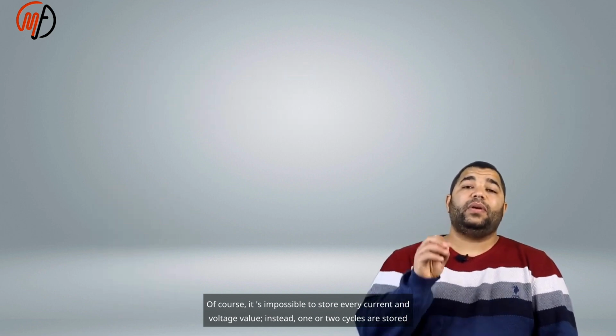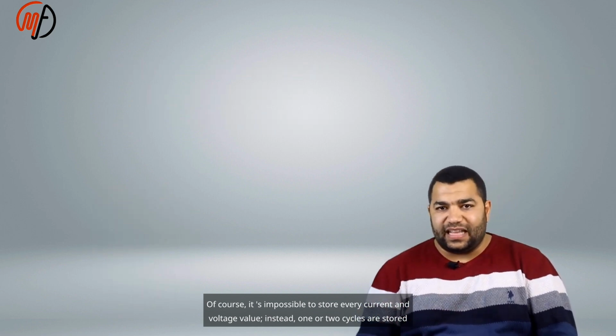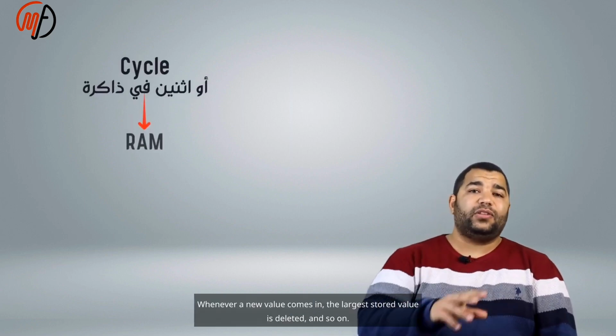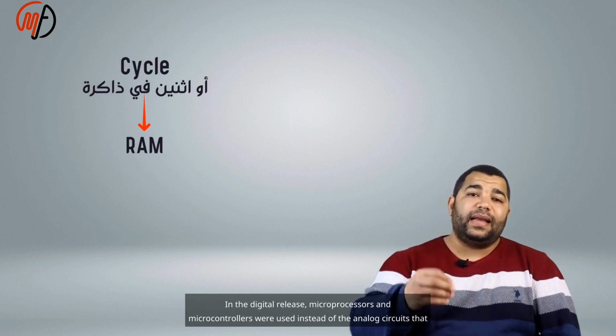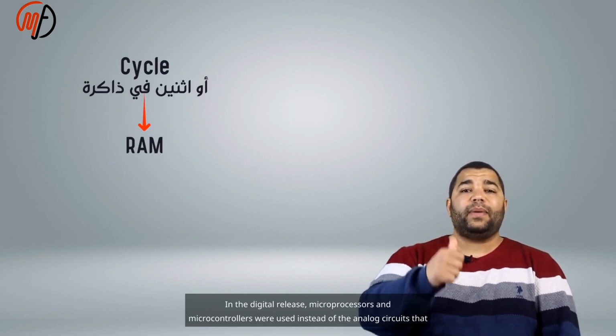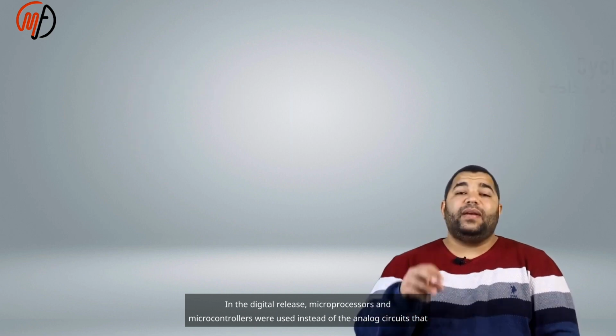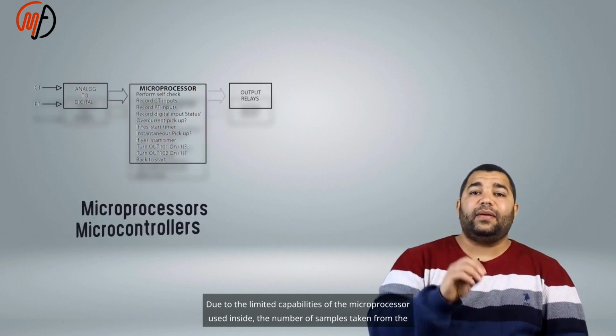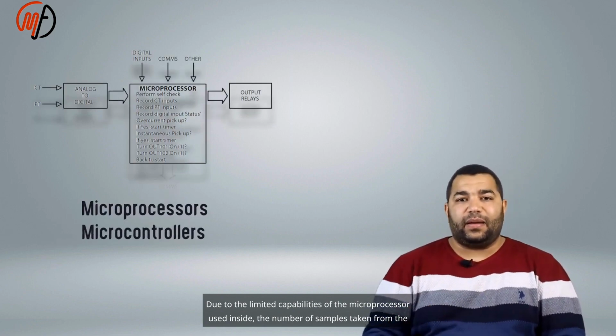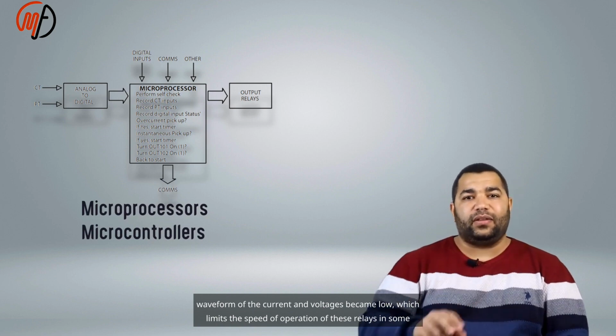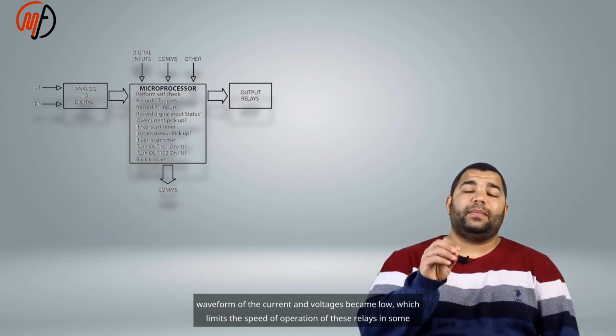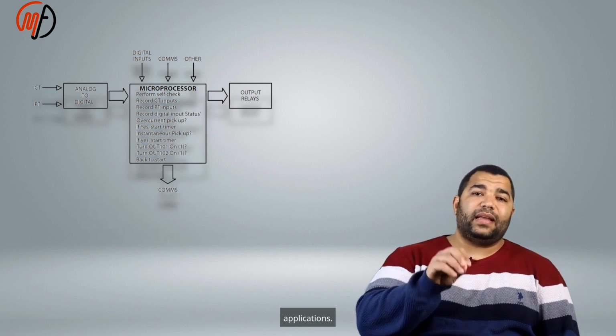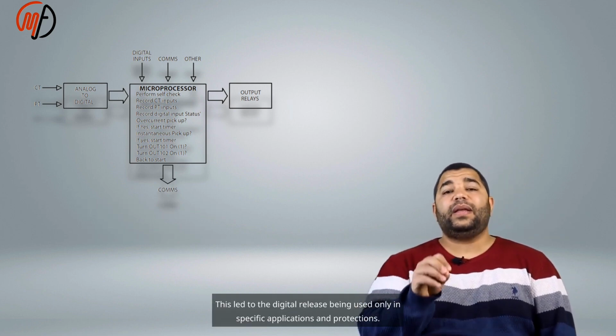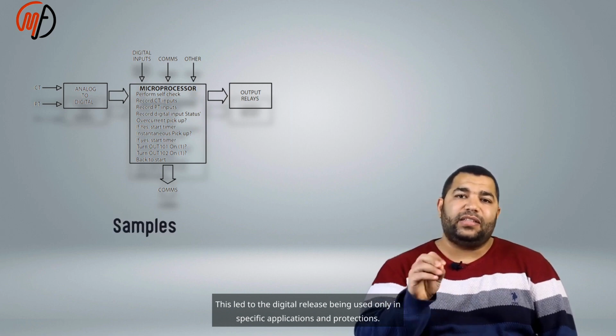Of course, it's impossible to store every current and voltage value. Instead, 1 or 2 cycles are stored in RAM. Whenever a new value comes in, the oldest stored value is deleted, and so on. In the digital relay, microprocessors and microcontrollers were used instead of the analog circuits that were used in the old static relays. Due to the limited capabilities of the microprocessor used inside, the number of samples taken from the waveform of the current and voltages became low, which limits the speed of operation of these relays in some applications. This led to the digital relay being used only in specific applications and protections.